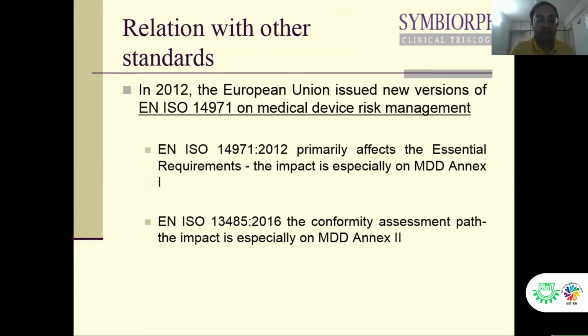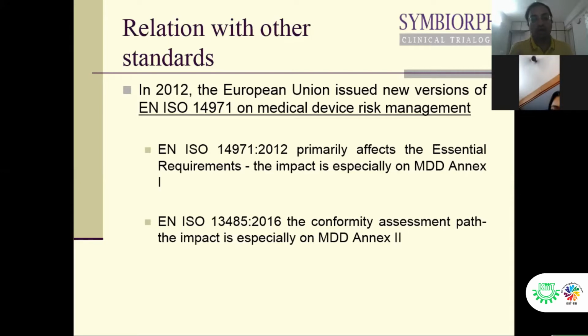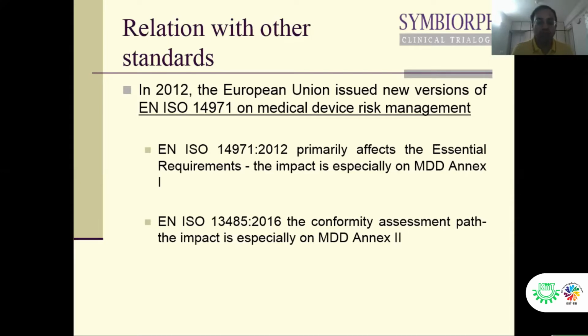Further to that, ISO 13485:2016 talks about the risk-based approach for your quality management system. So what do you mean by the risk-based approach? For the risk-based approach, the 13485 standard is now directly linked with the requirement of ISO 14971. And what is 14971?